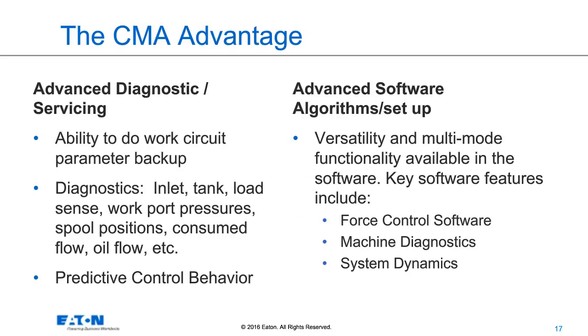As you also saw in the hardware, with all those sensors and its own control mechanism, we've really positioned this valve to have advanced diagnostics and servicing. One thing I touched on briefly was parameter backup. The VSM is programmed and maintains the database for each work section, function, and everything involved within that function and work section. Because of that parameter backup, a benefit we often see from a servicing standpoint is that if you have an issue with a work section, we have the capability to put on a new work section in the field, bleed the valve, and retrain it through the VSM, so we can get an OEM back up and running quickly.